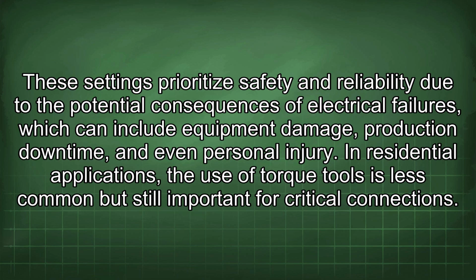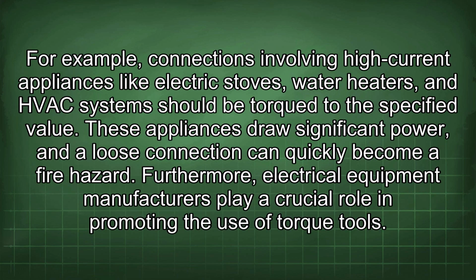In residential applications, the use of torque tools is less common but still important for critical connections. For example, connections involving high current appliances like electric stoves, water heaters, and HVAC systems should be torqued to the specified value. These appliances draw significant power, and a loose connection can quickly become a fire hazard.